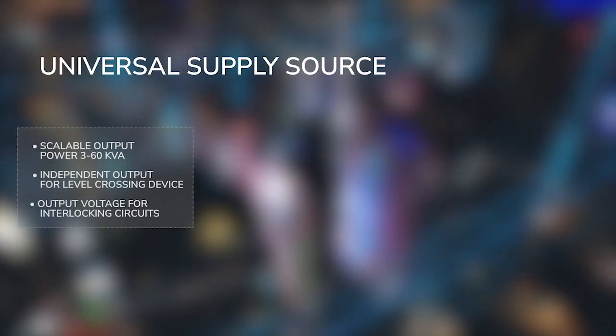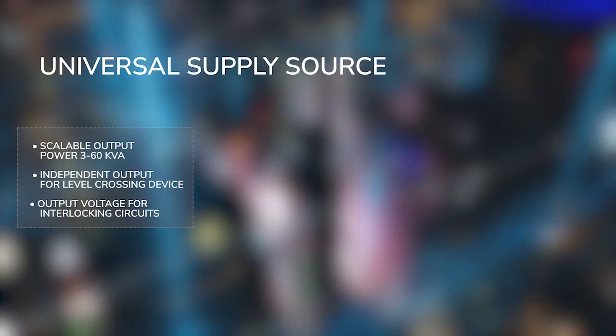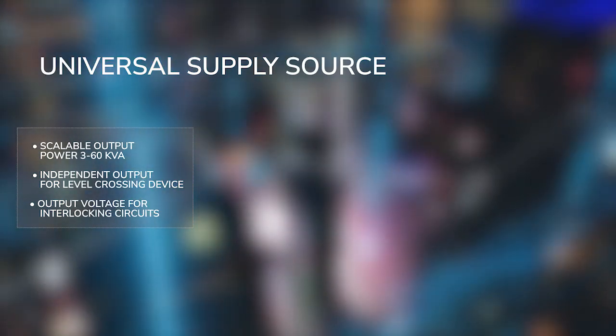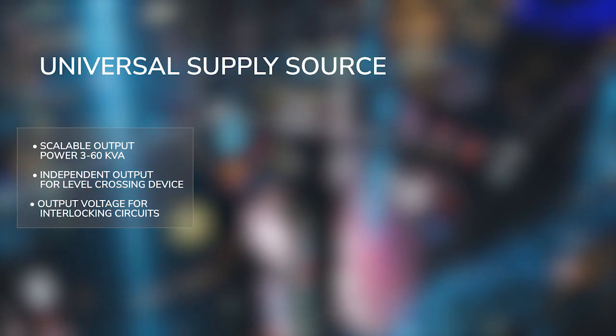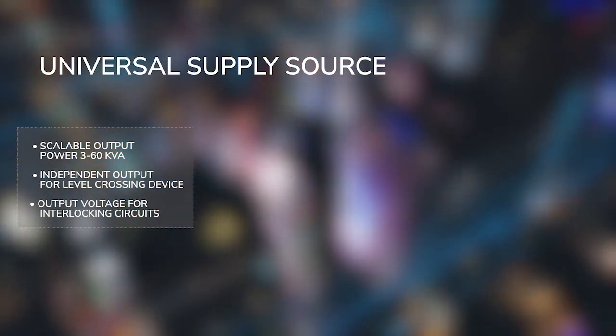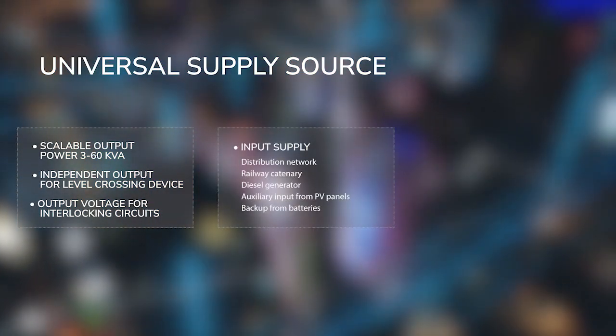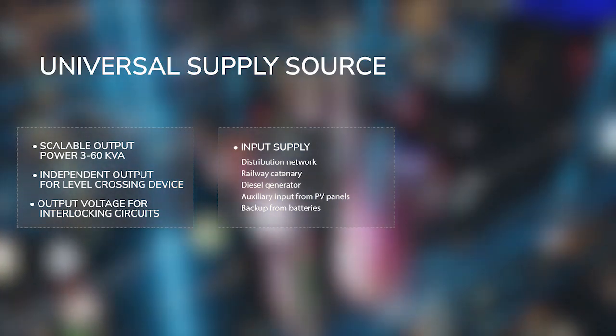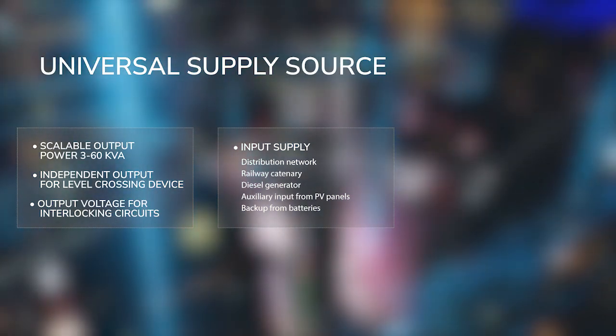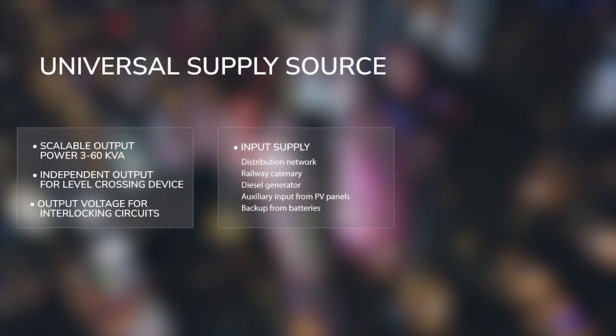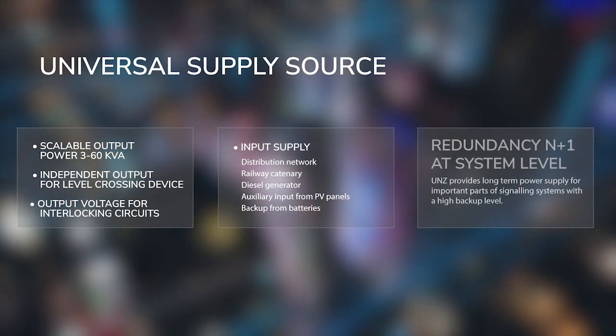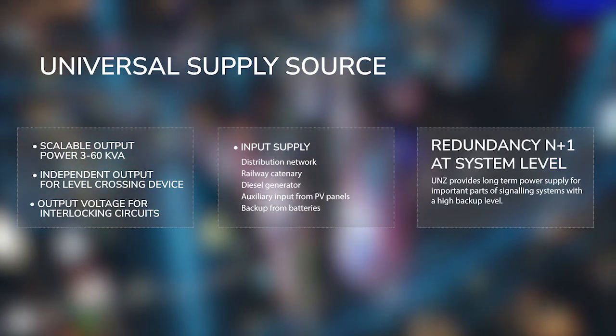Universal supply source. Scalable output power 3 to 60 kVA. Independent output for level crossing device. Output voltage for interlocking circuits. Input supply: distribution network, railway catenary, diesel generator, auxiliary input from PV panels. Backup from batteries. Redundancy N+1 at system level.